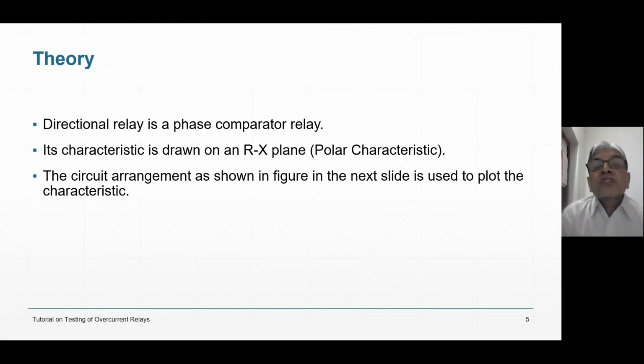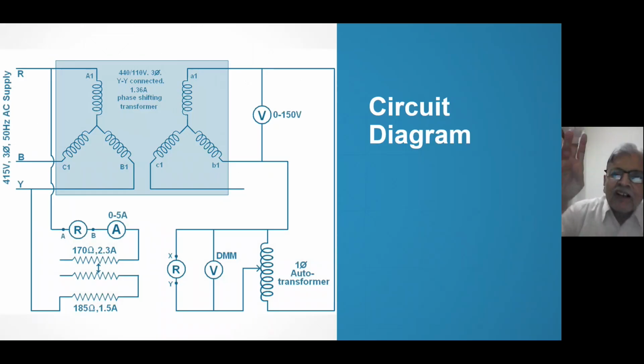So what is our theory? Directional relay is a phase comparator relay - it compares the angle between voltage and current. Its characteristic is a polar characteristic, drawn on the Rx plane. The overcurrent relay we were drawing on the IT plane, current versus time, but this is the Rx plane, resistance reactance plane. The circuit arrangement shown in the next slide is used to plot the characteristic. This much is only the theory.